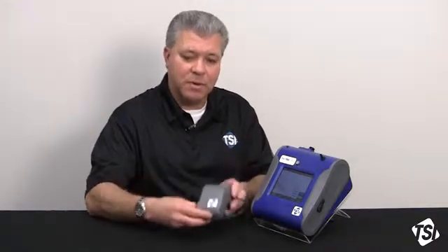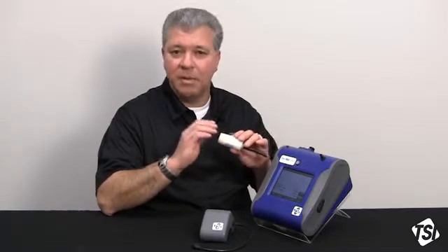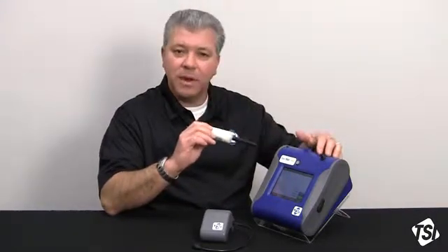Now, a couple of things. Why would we want to use an Auto Zero module for long-term sampling applications? There's really a variety of reasons. Number one, it's that long sampling time that's going to be taking place. During that sampling time, the electronics in any photometer will start to drift a little bit from their zero baseline. For short sample runs, like industrial hygiene applications where you may be running for 2 or 3 hours at a time, you can simply use a zero filter and do a zero calibration on the instrument. Well, you don't have that luxury when you're doing a long-term sample for 24 hours, say in an office building overnight during the next day, and the same thing for 24/7 monitoring for fugitive emissions.